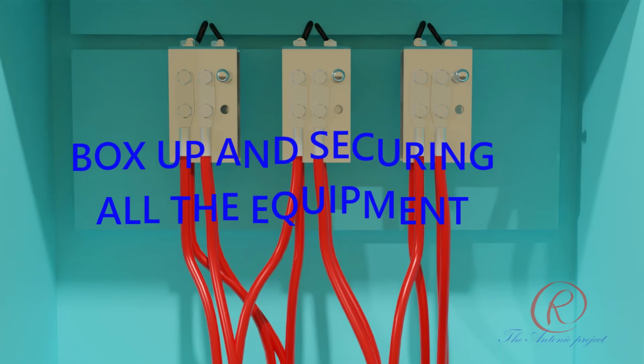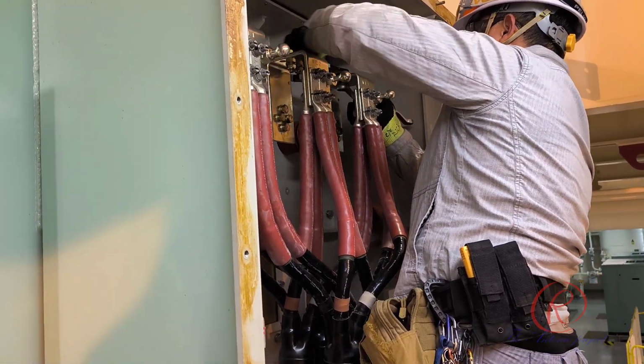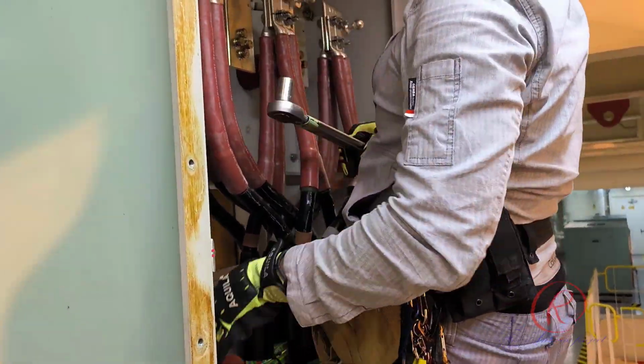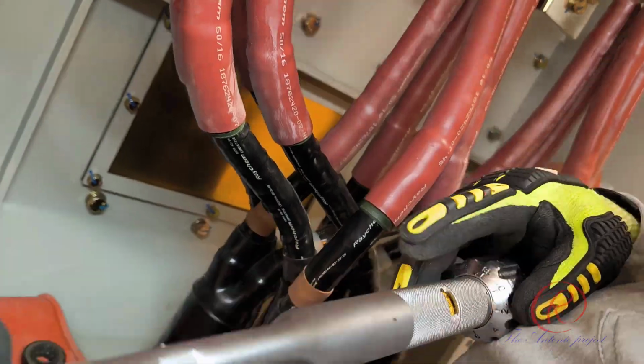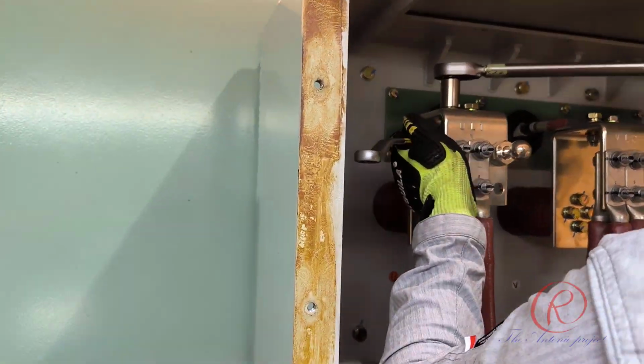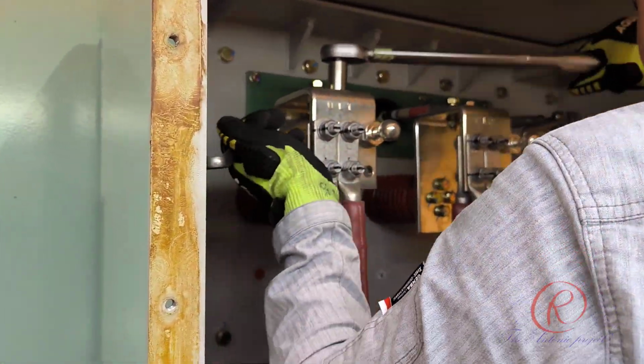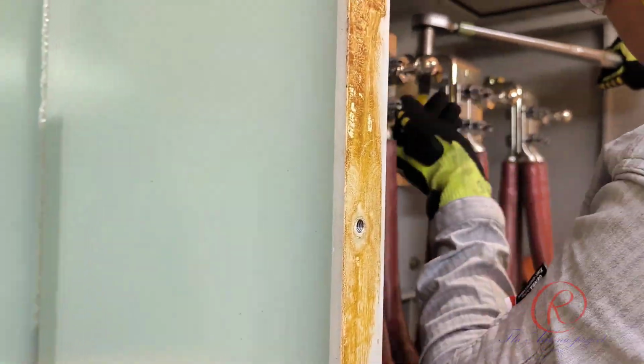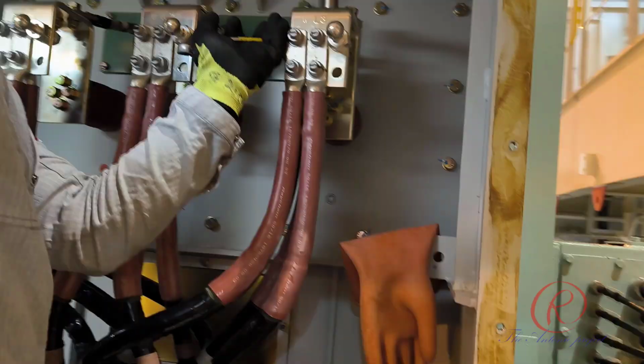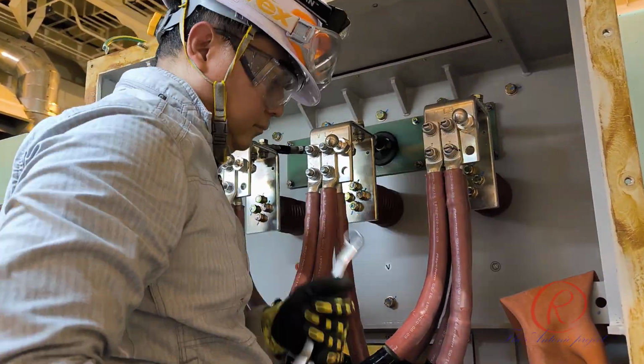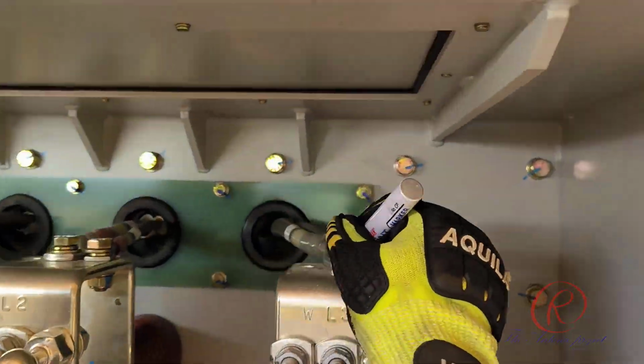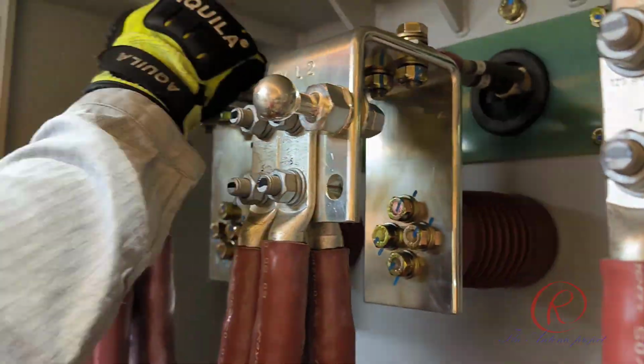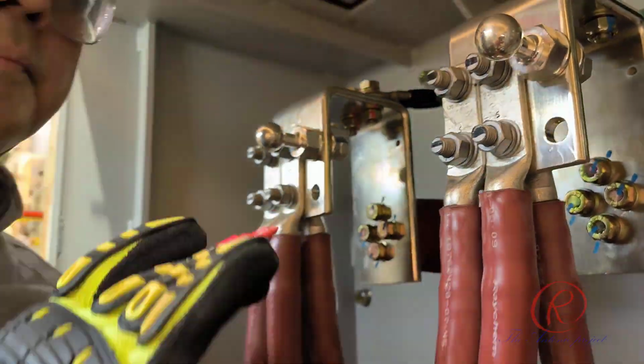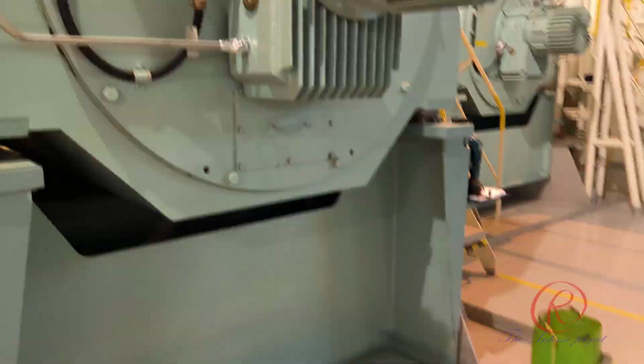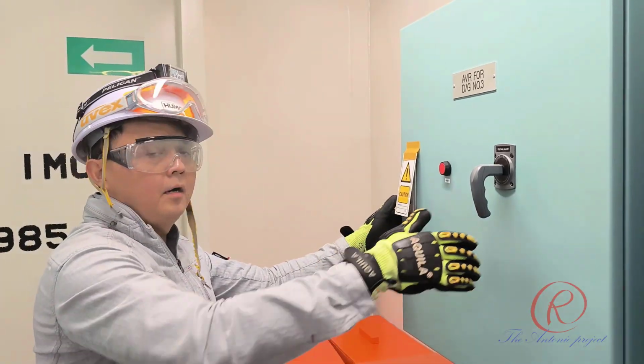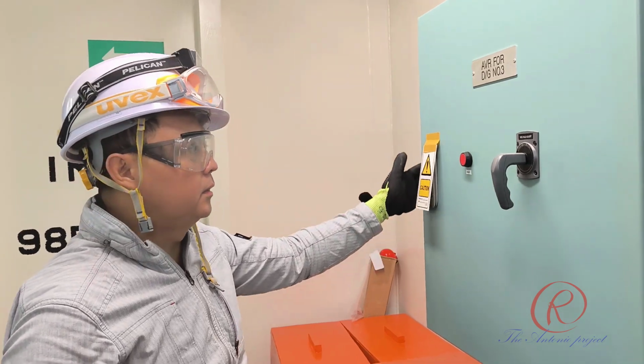Box up and secure all the equipment. After completion of all maintenance works, set back all cables and carry out tightening of bolts by applying torque at the specified value. Apply marking on each nut after completion of torque tightening in order to confirm that the lock nut is not slipping during service. After completion of work, return back all the system.